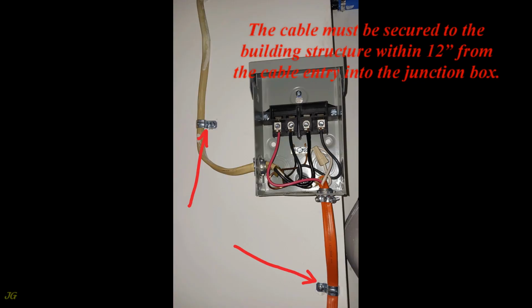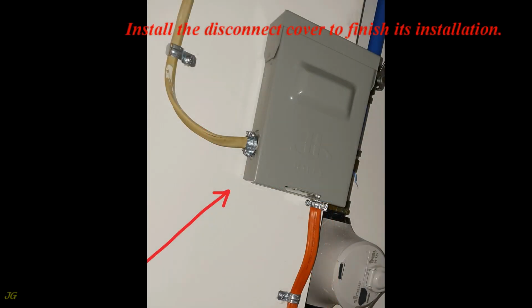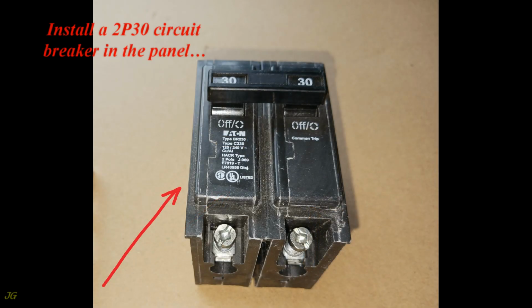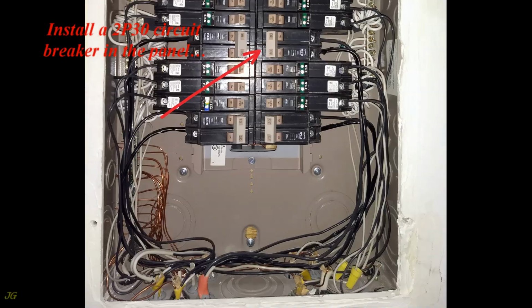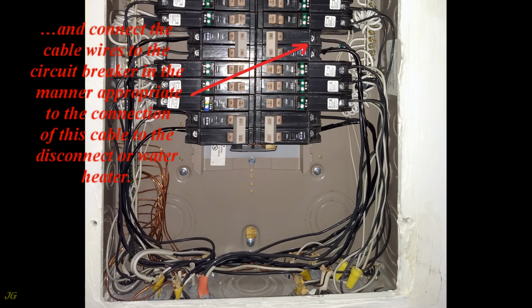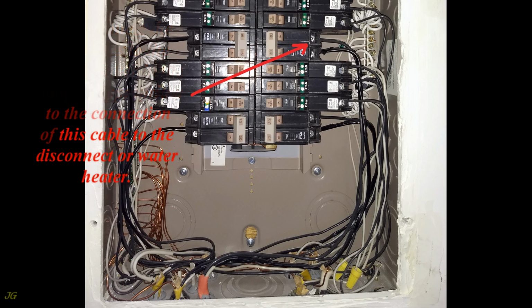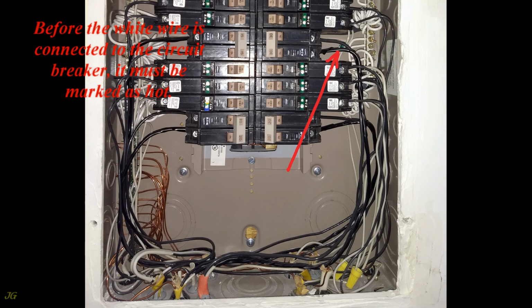The cable must be secured to the building structure within 12 inches from the cable entry into the junction box. Install the disconnect cover to finish its installation. Install a 2-pole 30 amp circuit breaker in the panel. Insert the cable through an approved cable connector, and connect the cable wires to the circuit breaker in the manner appropriate to the connection of this cable to the disconnect or water heater. Before the white wire is connected to the circuit breaker, it must be marked as hot.